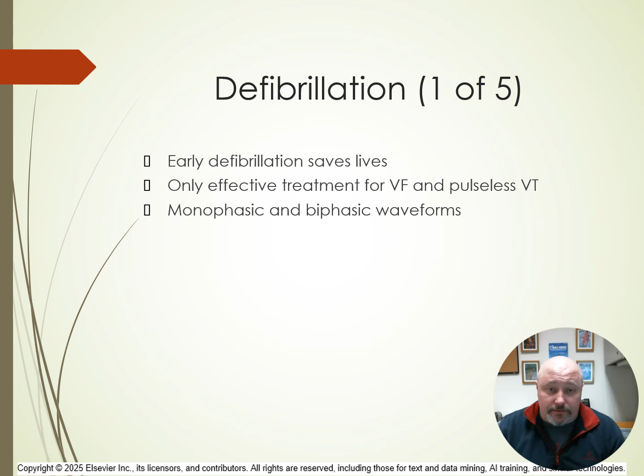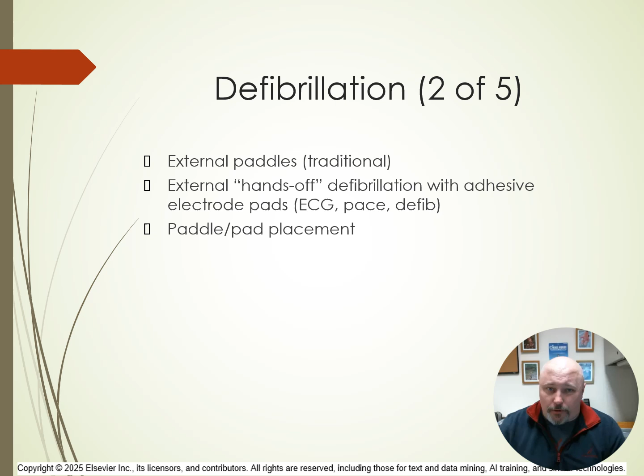Paddles have been used for years and require conductive gel or pads for efficient delivery of current. The pads are more commonly used and allow safer defibrillation via a hands-off approach, meaning you don't have to be as close to the bed, as anyone touching that patient or the bed does have the risk of electrical shock and injury. So regardless of type, correct paddle and pad placement is going to be key.